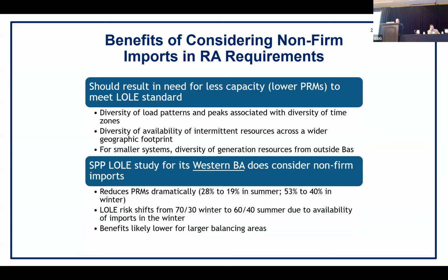So just at a super high level, what are the benefits of looking at non-firm imports when you're setting a planning reserve margin? As it says here, it should result in less capacity or lower planning reserve margins to meet that same LOLE standard. When you consider diversity of load patterns, different time zones in particular would be really helpful to help shift those peaks.